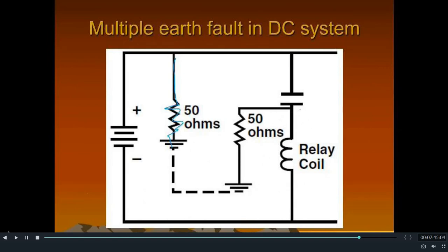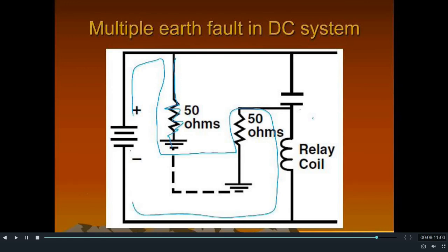Now we will see the case of multiple earth fault or double point to earth fault. As shown in the figure, there is an earth fault in the positive arm of the battery as well as on the negative arm of the battery, and the negative arm fault is also after the relay coil. In such cases of double earth fault, the whole battery voltage V will get discharged through the relay coil and will come back to the battery negative terminal. Hence a rated current will flow through the relay or circuit breaker coil, which will be able to actuate it. Hence in such cases only there will be mal tripping in the system. Friends, if you like the video please like, share, and comment, and don't forget to subscribe to the channel.